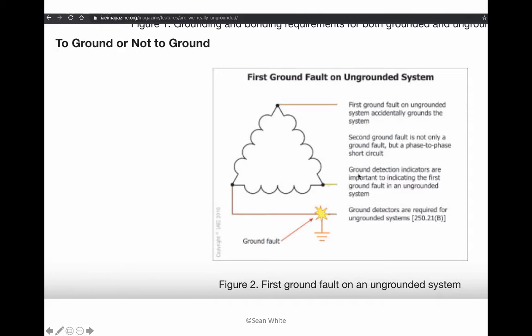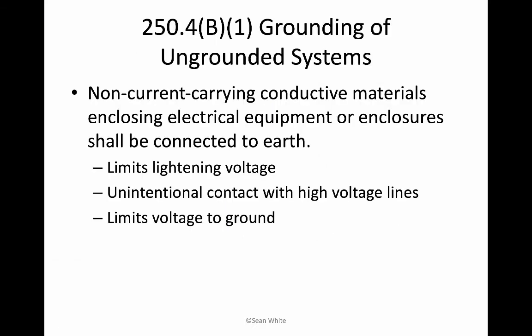Then what we can see there, it says ground detection indicators are important. Of course, you want to have that. And so there is the second ground fault. And you don't want to have the second ground fault in a system like this. And back to 250.4(B)(1), grounding of ungrounded systems. This is grounding, connecting to earth, not bonding, because (B)(2) is going to be bonding.